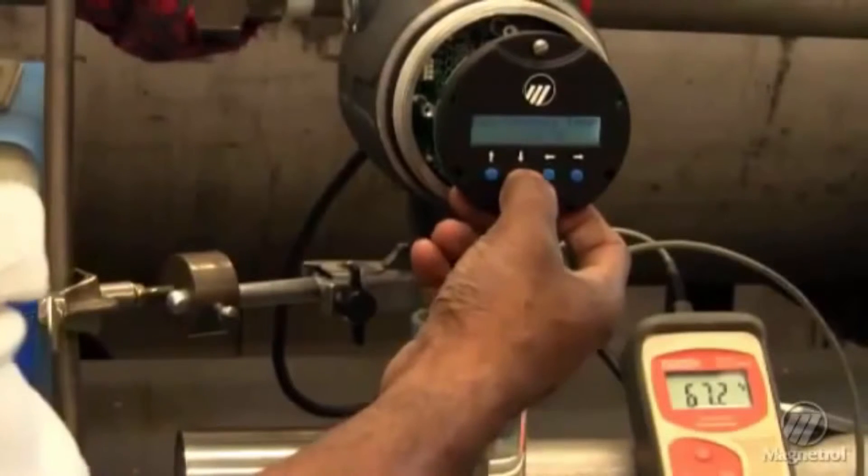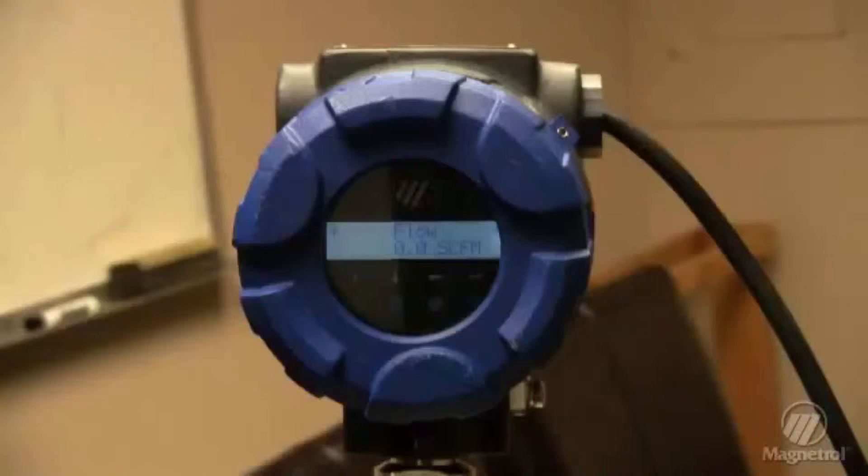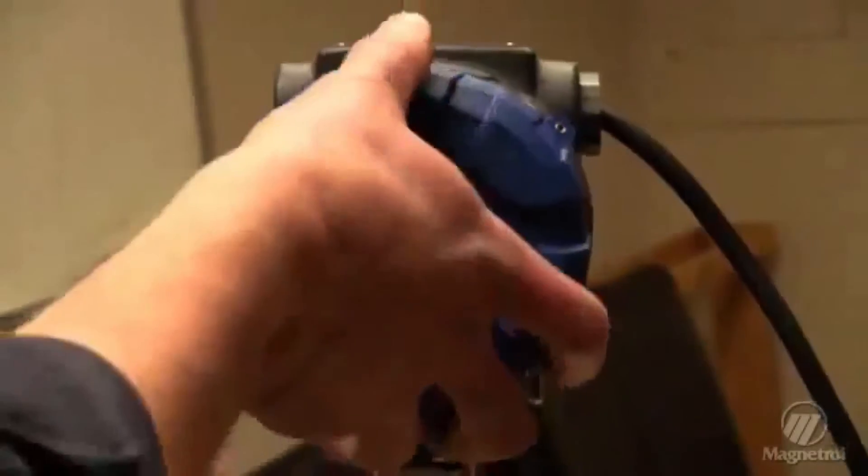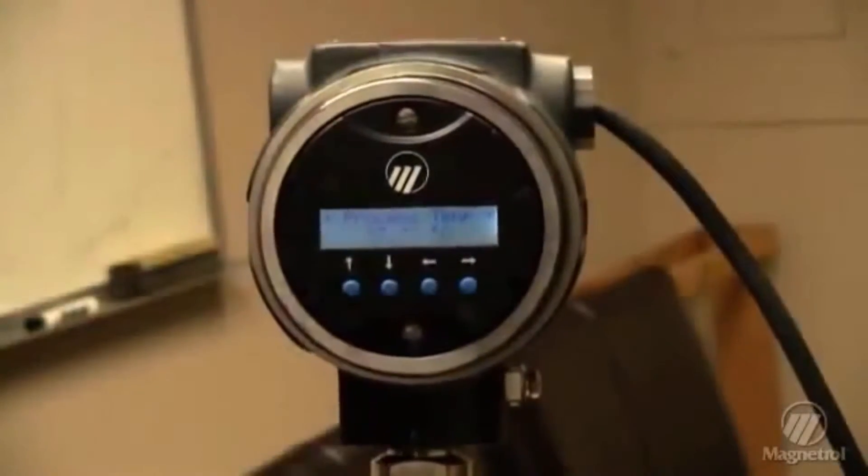These procedures should be conducted at room temperature. The first test is a low flow validation. During the test, the heater power is set and the temperature difference between the RTDs is measured.